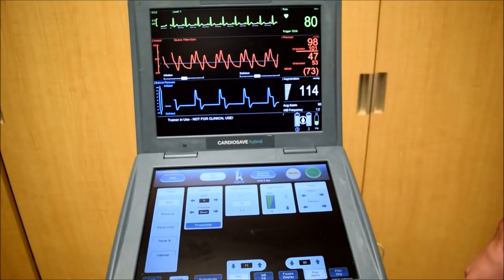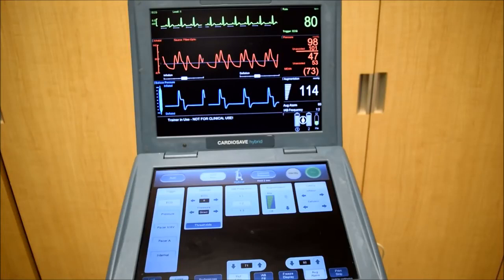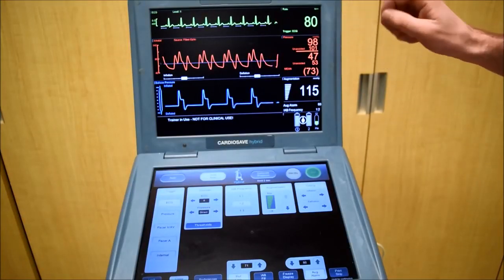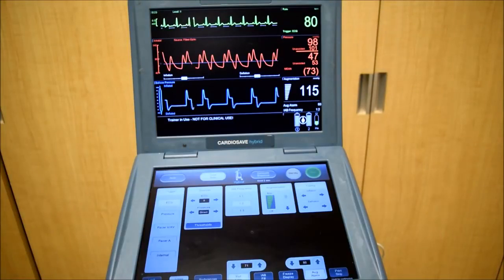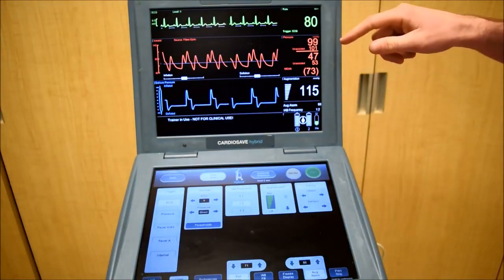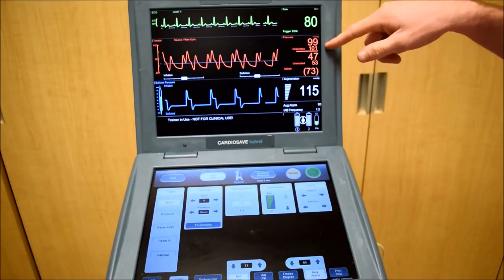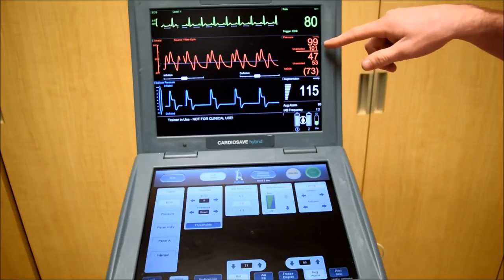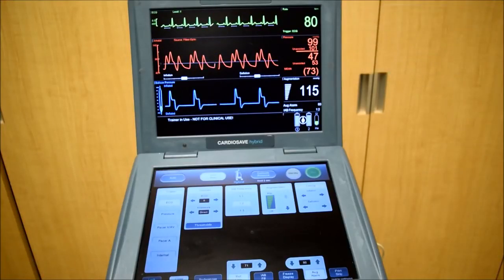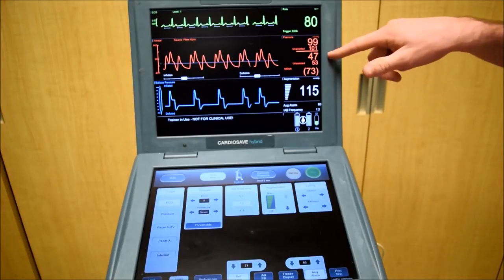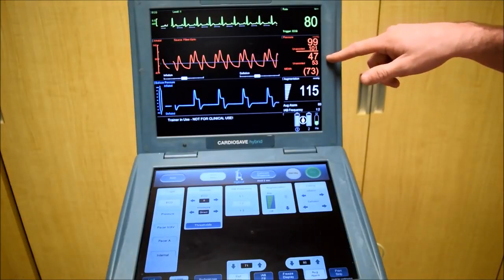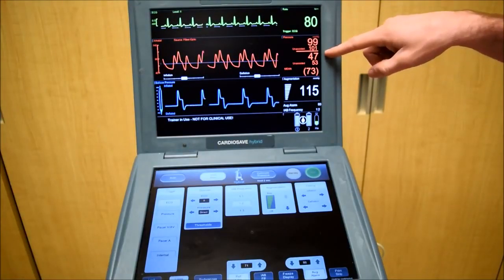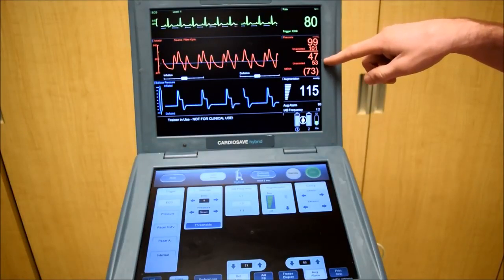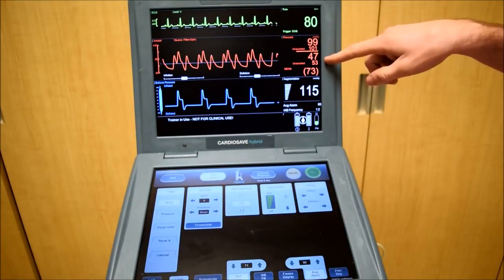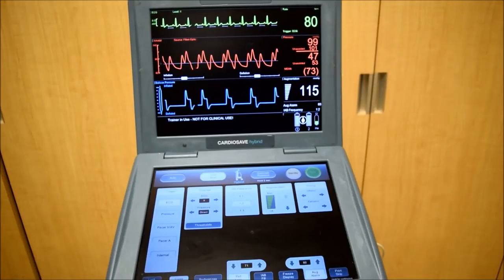If you're looking at the patient's monitor, you may notice that the monitor doesn't recognize the difference between assisted and unassisted, and it'll assume the systolic pressure is the unassisted, or the higher, the 101. Similarly with the diastolic, a monitor may recognize the assisted 47 instead of the unassisted 53. The mean should always stay the same though.